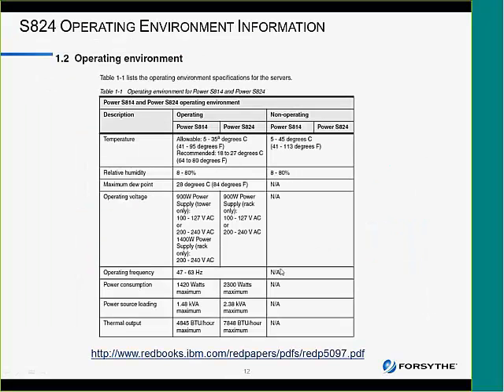So this is right out of the Red Book. I put the actual full link down here. This is the technical overview for the 824. And so what this is showing you is the operating environment. And the things we're looking for here, this is the 814, this is the 824. So the operating power is 900 watts, but the maximum is 2300 watts. So I plan on the 2300. I use the 2.38 kVA here and the 7848 BTUs per hour. Those are my planning numbers.